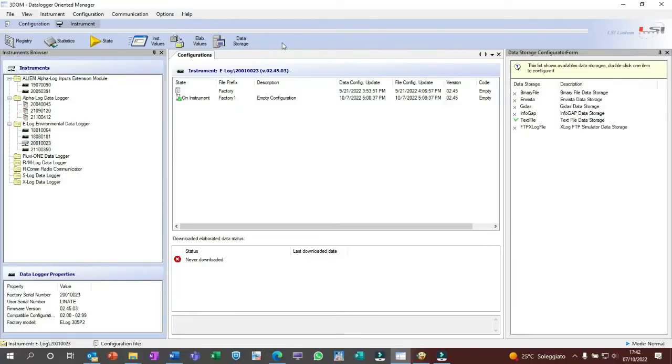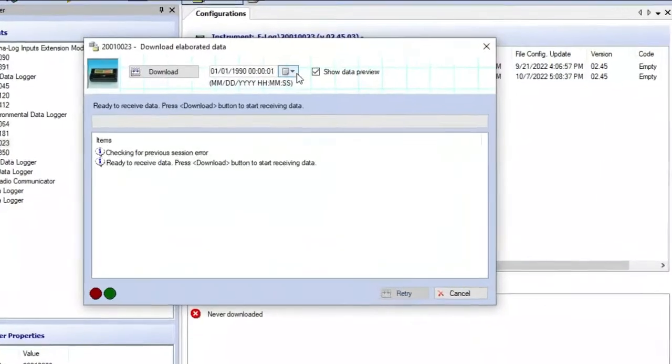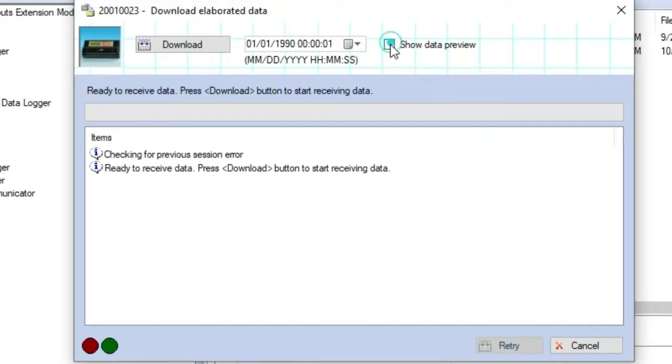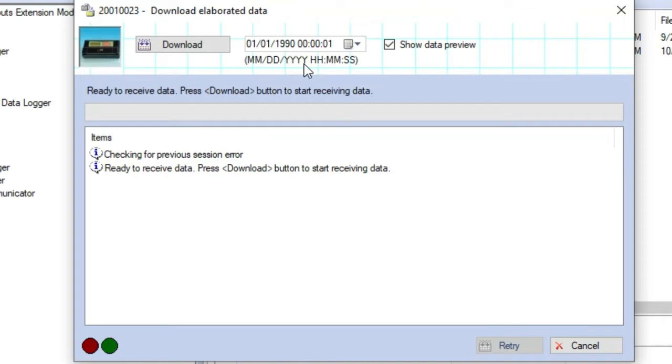Click on elaborated values button. Here we can tick if we want to get a data preview before downloading them. Here we can set a date and time from when data stored in the E-Log memory can be downloaded. If we don't select any date, 3DOM will start downloading data starting from the date of the last downloading procedure made by this PC. Otherwise, selecting a specific date and time will be possible to force 3DOM to download them from such date.